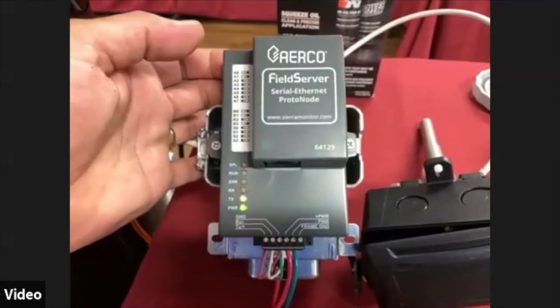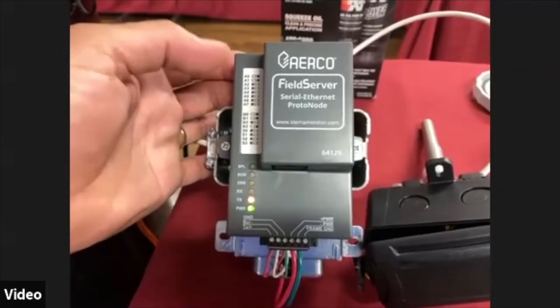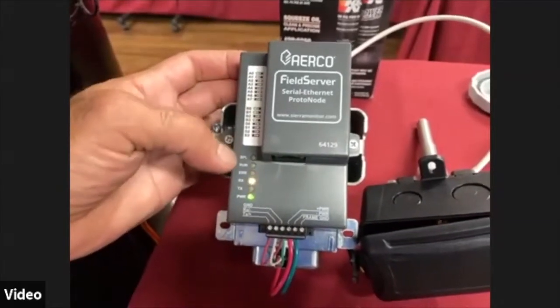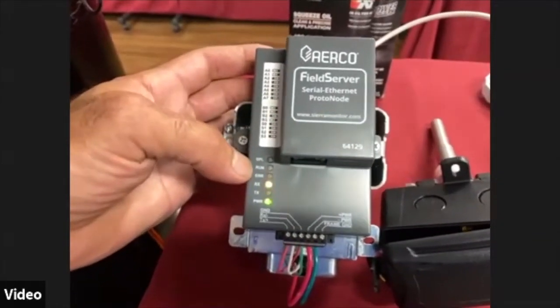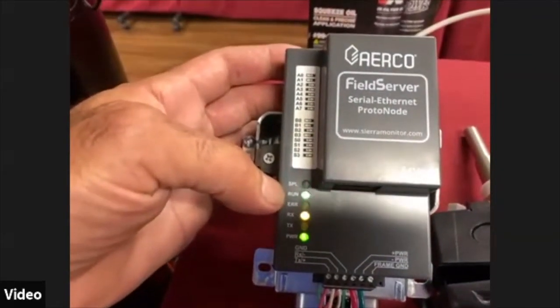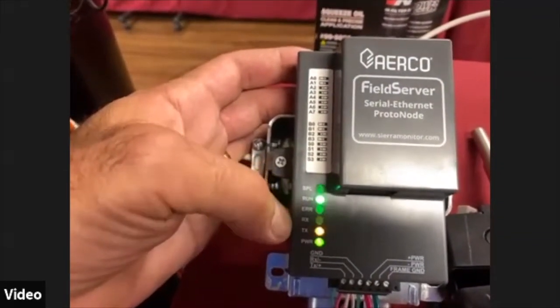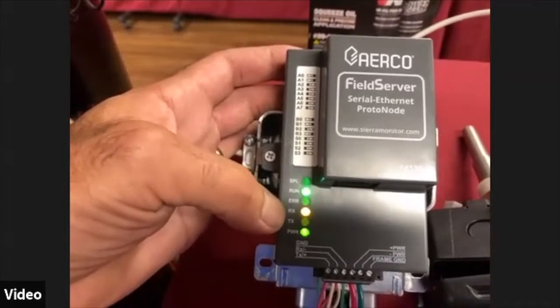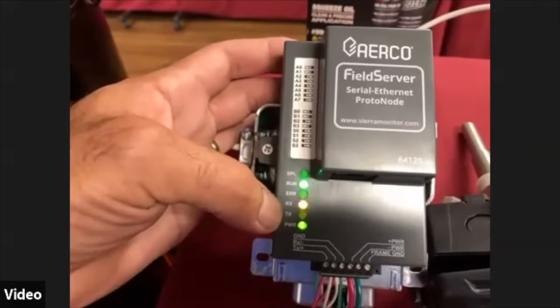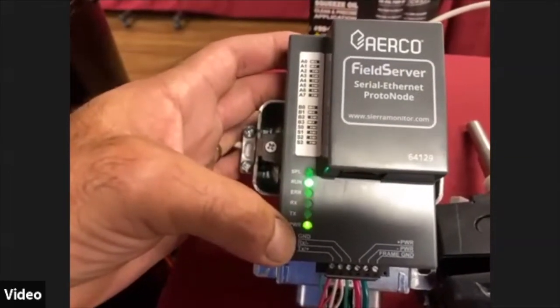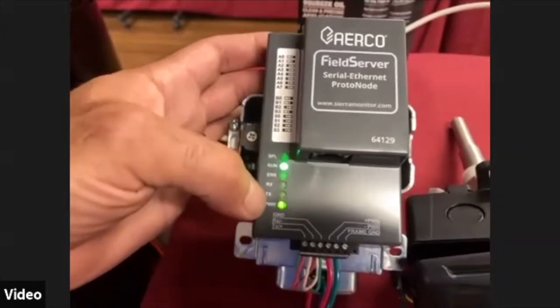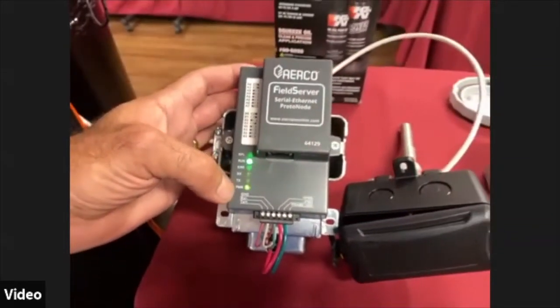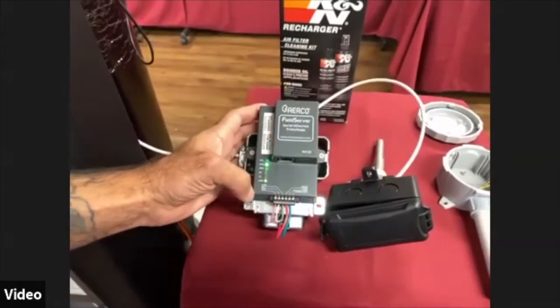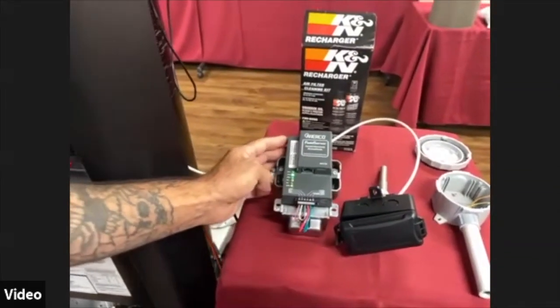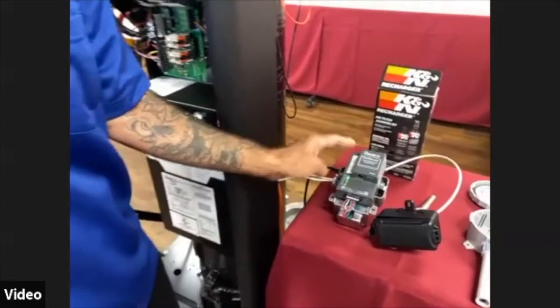So that we know on our end, from the boiler at least to the gateway, whether we're communicating, this is what we're looking for. We're looking for a slow flashing run light, rapidly flashing RX and TX, which are receive and transmit lights, and a solid green power light. Anything other than that, the profile may not be set up correctly, and you may have to look at resetting up that profile. So just verify you got everything set up correctly.